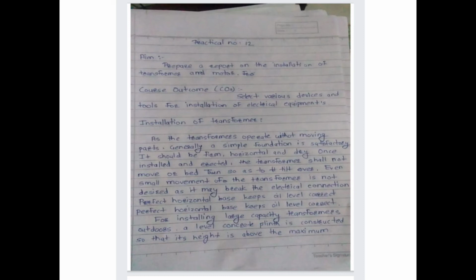Course outcomes are: select various devices and tools for installation of electrical equipment and the installation of transformer. As transformers operate without moving parts, generally a simple foundation is satisfactory. It should be firm, horizontal and dry once installed and erected. The transformer shall not move or bend so as to tilt over. Even small movement of the transformer is not desired, as it may break the electrical connections.